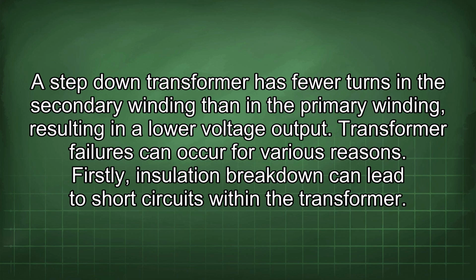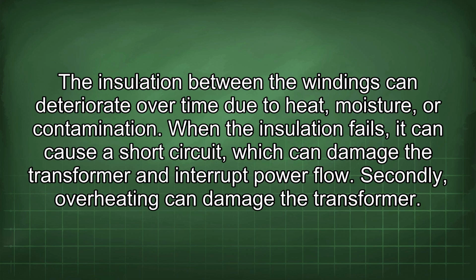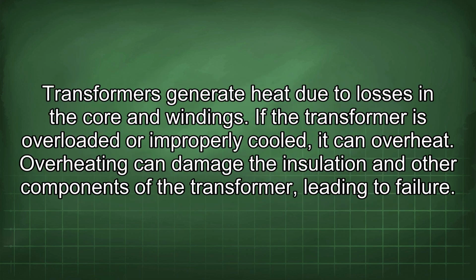Firstly, insulation breakdown can lead to short circuits within the transformer. The insulation between the windings can deteriorate over time due to heat, moisture, or contamination. When the insulation fails, it can cause a short circuit, which can damage the transformer and interrupt power flow. Secondly, overheating can damage the transformer. Transformers generate heat due to losses in the core and windings. If the transformer is overloaded or improperly cooled, it can overheat. Overheating can damage the insulation and other components of the transformer, leading to failure.